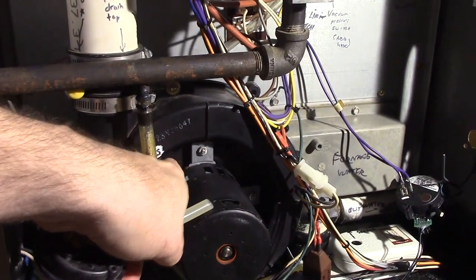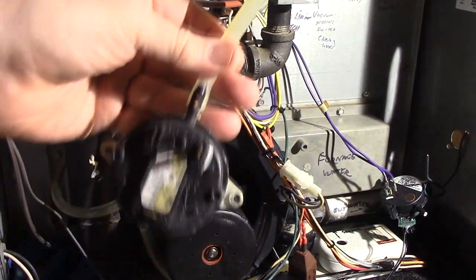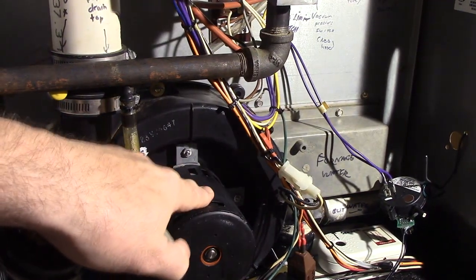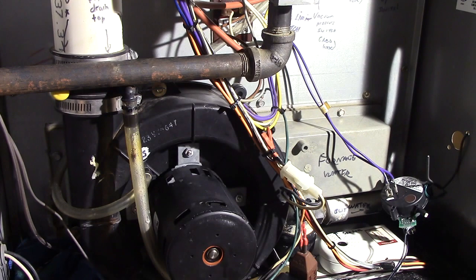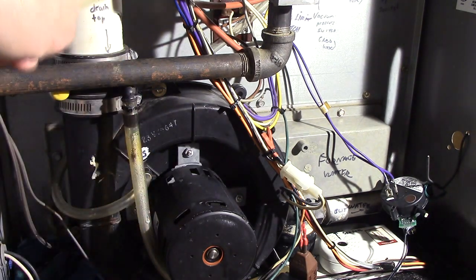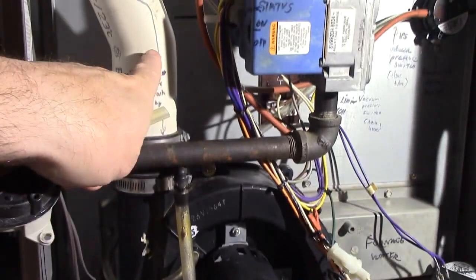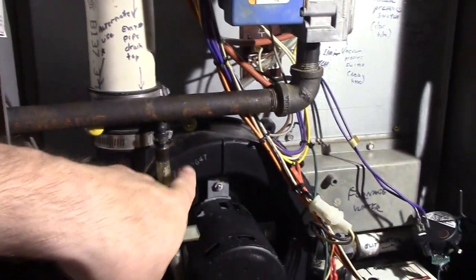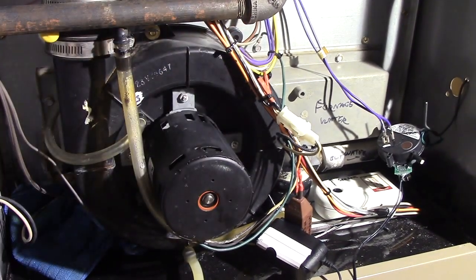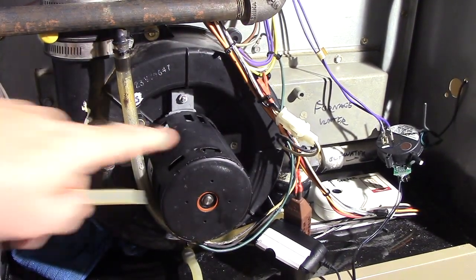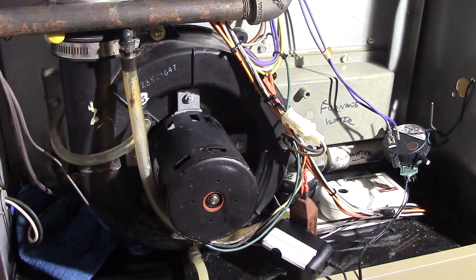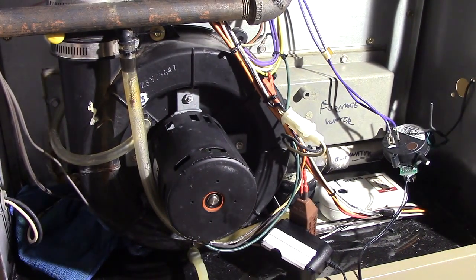can't see. That tap is what goes to the pressure switch. The inducer kicks on and a vacuum is created. This is a drain which gets water from your outside water collection tube, but there's a tap right there that will trigger the pressure switch. It doesn't trigger immediately because it has to build up vacuum - that's what the computer on the furnace wants. They're all the same.